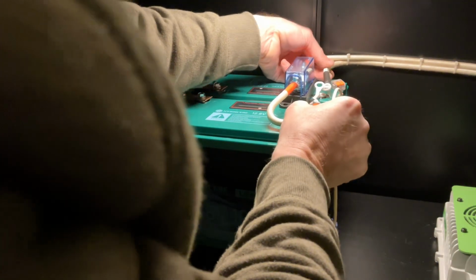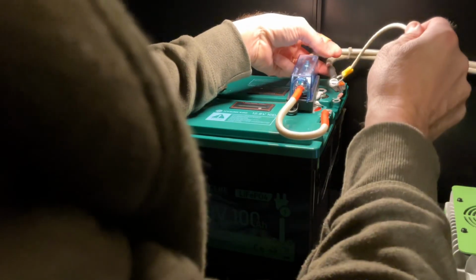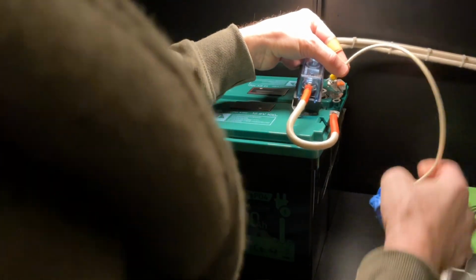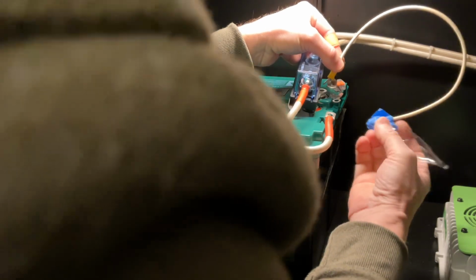Since these leads were previously connected directly to the inverter, I'm going to check if there's any charge left in the capacitors of the inverter by discharging it with a simple light bulb. You can see there was still charge in the capacitors, over 50 volts on these wires going to the inverter. That's something to remember when you disconnect wiring from a system connected to a large inverter — they have a massive capacitor bank and can store energy for quite some time.